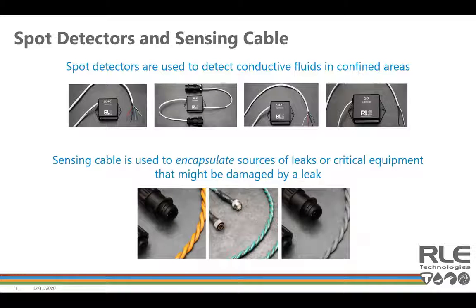Once you determine what it is that you need and want to protect, you can deploy spot detectors. They're used to detect conductive fluids in confined areas, such as drip pans or floor drains, or you can use sensing cable laid out around room perimeters or affixed to water supply pipes, or a combination of both. We have 4 different types of spot detectors. The SD-RO1 has a relay output and can be used with products that accept a dry contact input, so you don't need an RLE controller for this one. The SDZ, SDZ1, and SD are all compatible with certain RLE leak detection controllers and also some of our facility monitoring products, giving a nice crossover between monitoring and leak detection products in place.